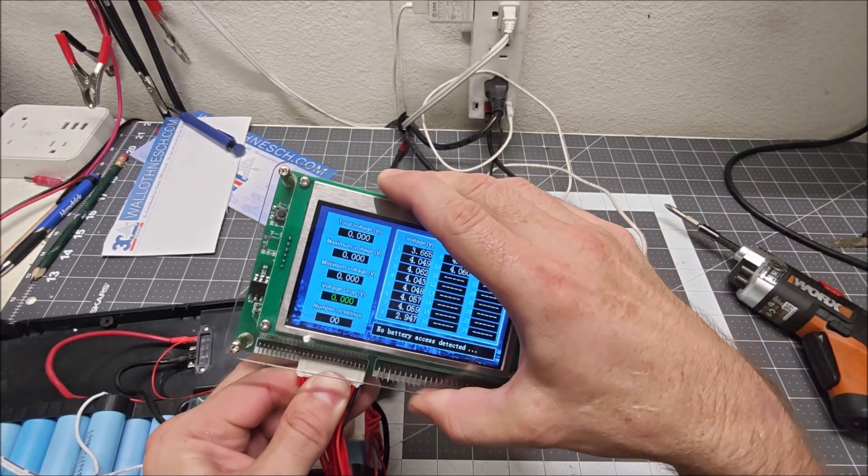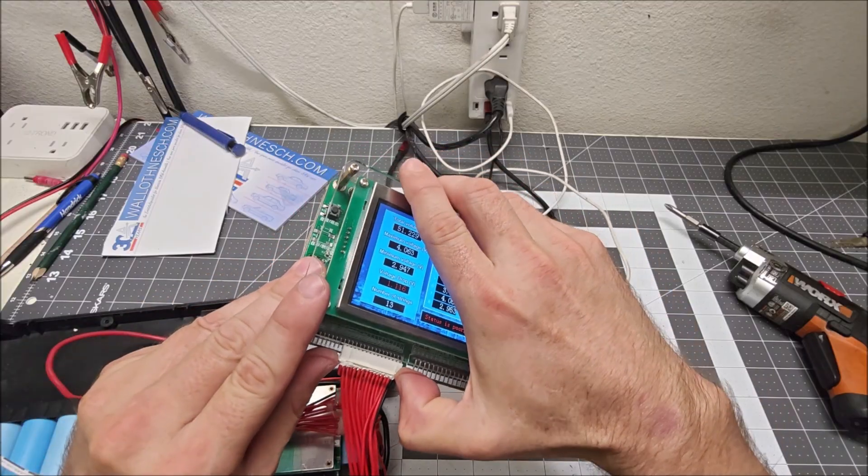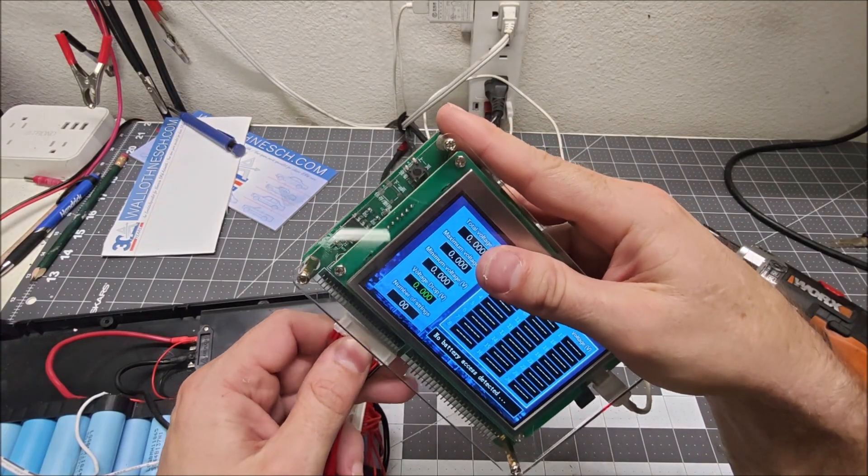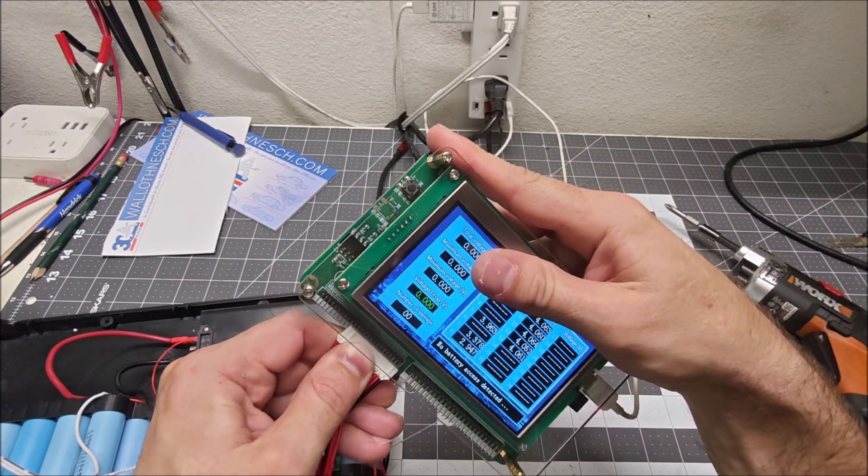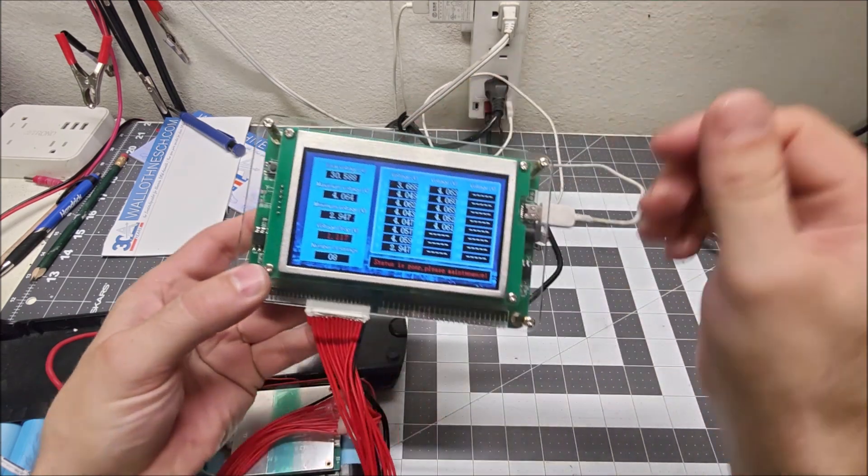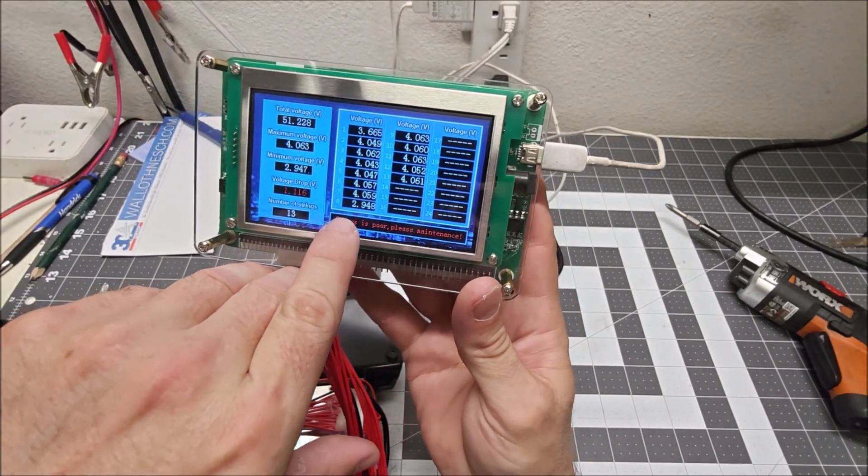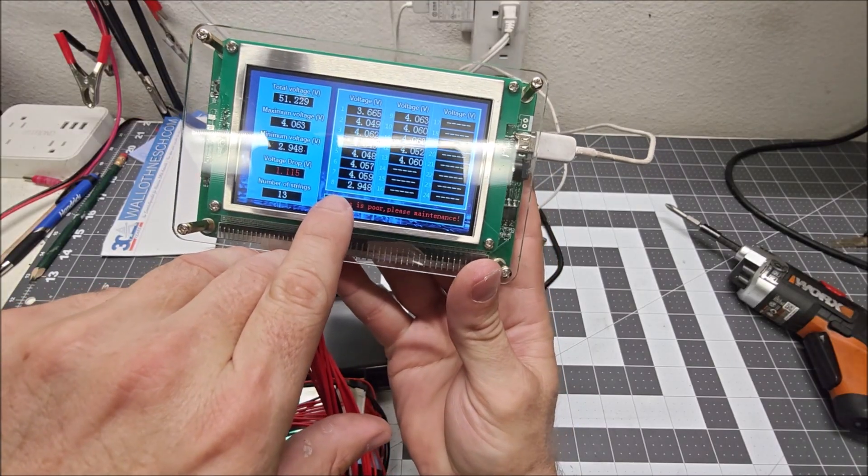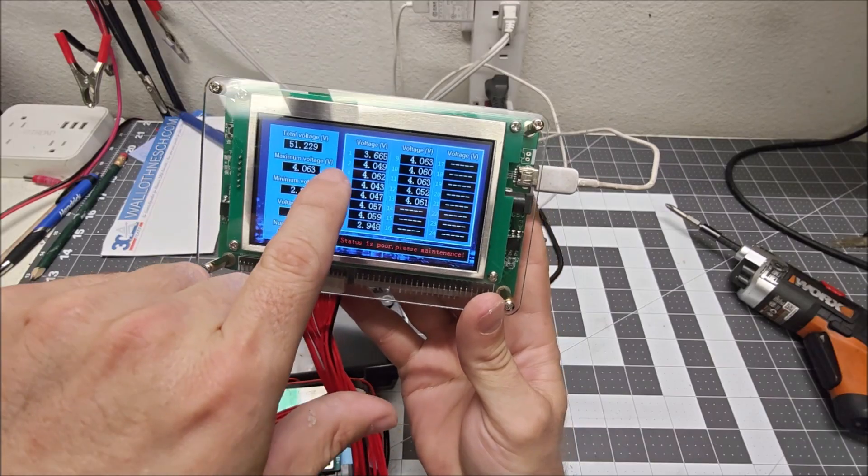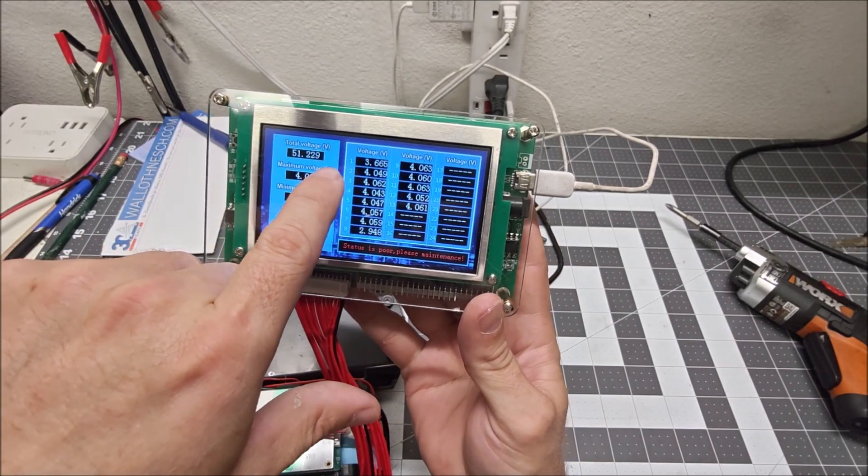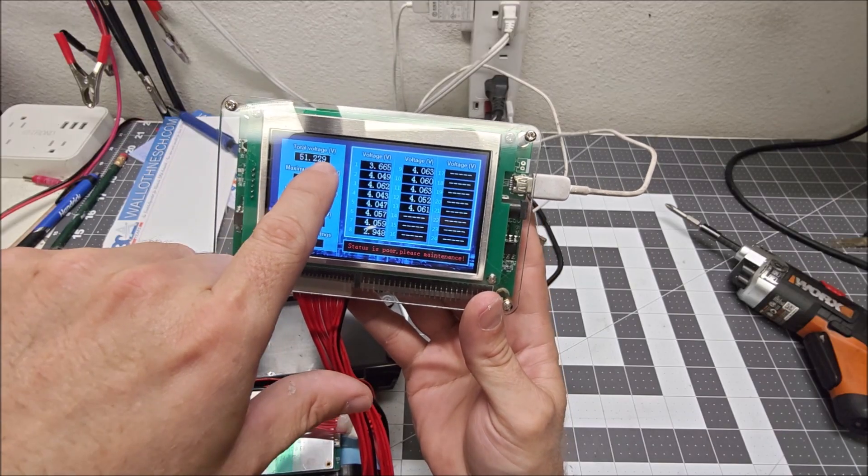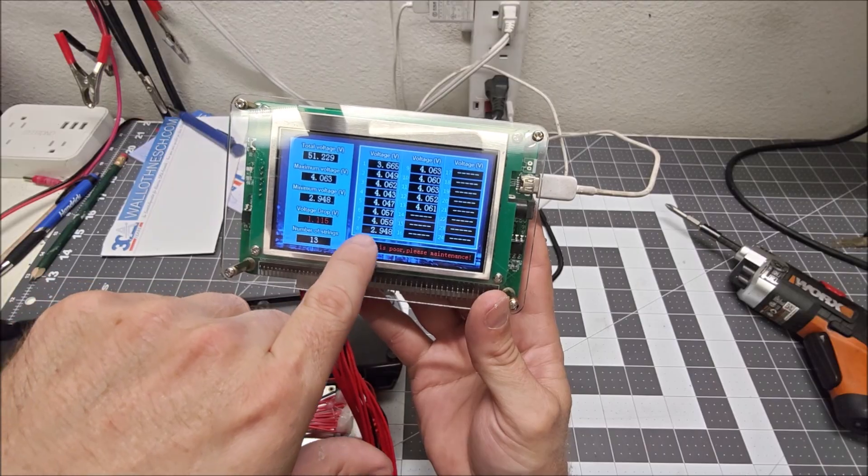Okay, that's on there. Let's see what it says. Oh, I already see the problem. These pins are a little fiddly to get on, but don't force it because you don't want to bend these pins. Do you see? Group number 8 is 2.9 volts, so there is a bad cell in group number 8, and group 1 also has a slightly bad cell. But the rest are all perfect at 4.0.